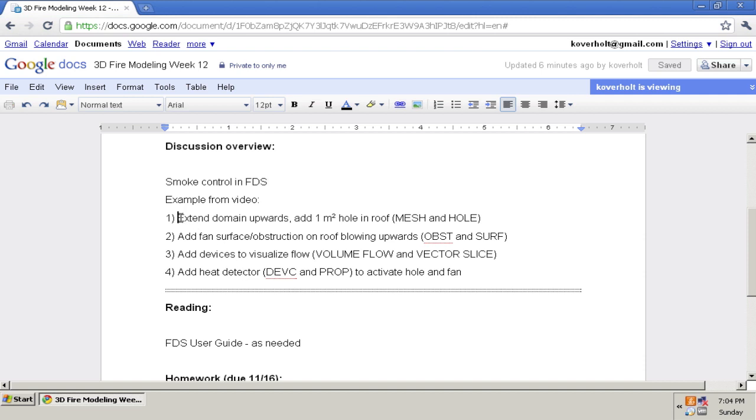So first I'm going to start with the room fire case, which is an example case that comes with FDS. The first thing, I'm going to extend the domain upwards and add a one meter square hole in the middle of the roof. Second, I'm going to add a fan surface/obstruction on the roof, which is blowing out air. Third, I'm going to add some devices that can help you visualize the flow and check to make sure that you're getting the correct volume flow rate. And finally, I'll add a heat detector to activate the hole and the fan.